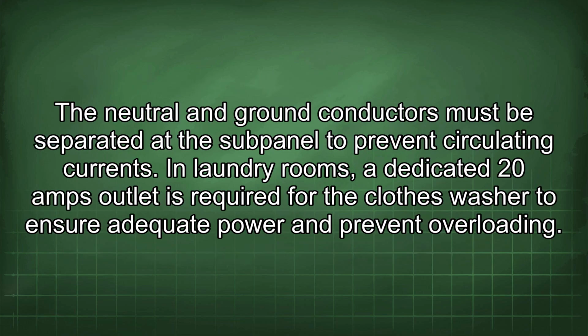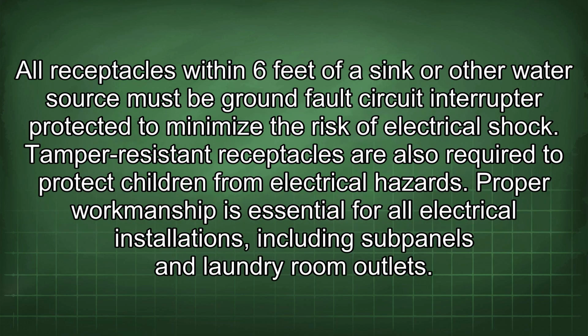The neutral and ground conductors must be separated at the subpanel to prevent circulating currents. In laundry rooms, a dedicated 20 amp outlet is required for the clothes washer to ensure adequate power and prevent overloading. All receptacles within 6 feet of a sink or other water source must be ground fault circuit interrupter protected to minimize the risk of electrical shock. Tamper-resistant receptacles are also required to protect children from electrical hazards.